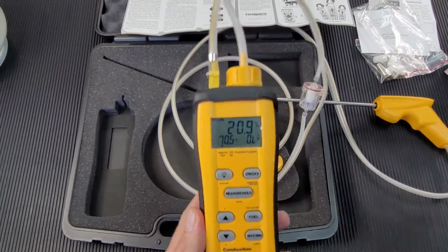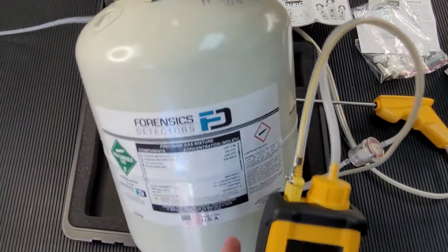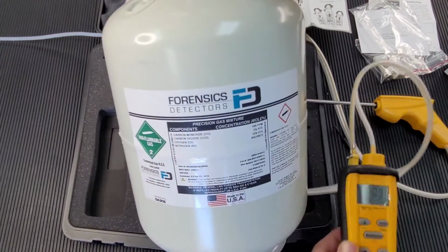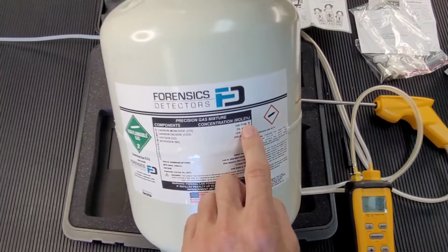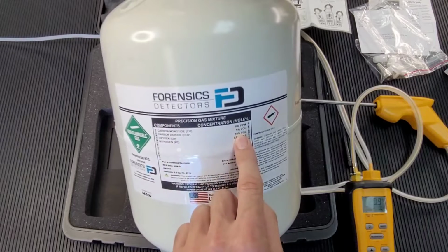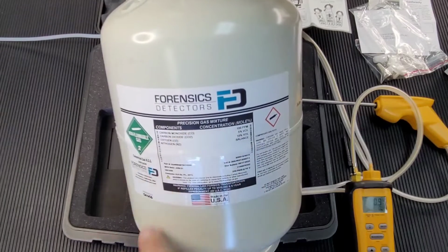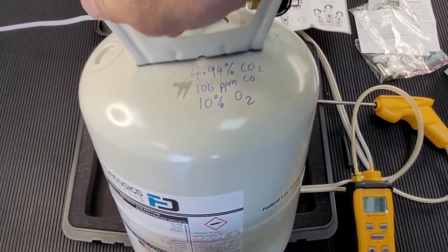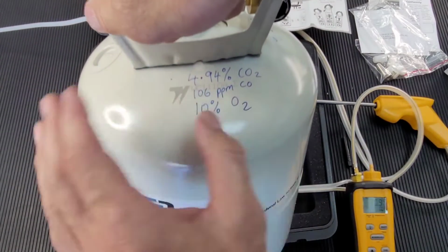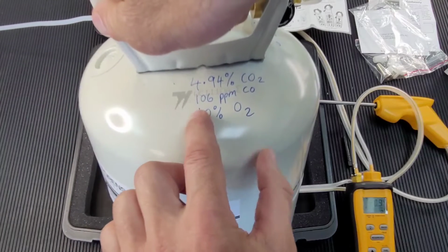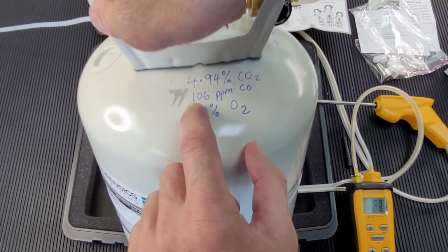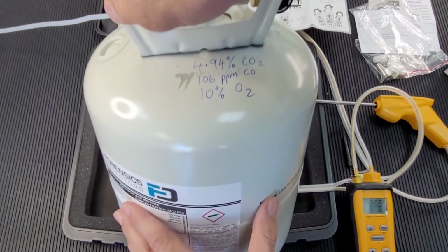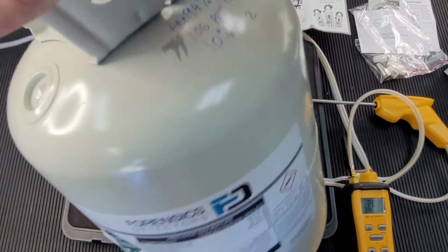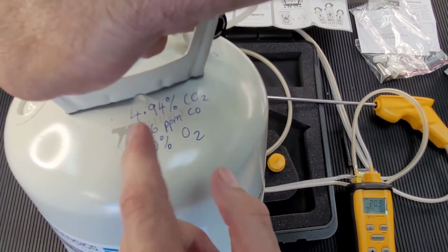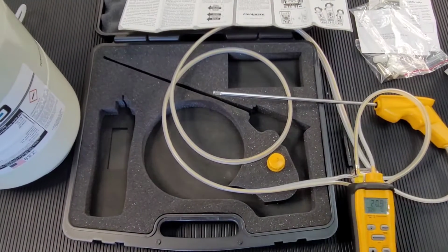Okay, so what we're going to do now is I'm going to rig it up for a test to my calibration gas, which is right over here. It has carbon monoxide 100 ppm, oxygen at 10%, and we have nitrogen and carbon dioxide. Okay, folks, sort of mimicking a situation in a combustion. Although, of course, there should be more of this or more of that. That's fine. Now, the certificate of analysis wasn't 100 ppm, it was 106. Although I ordered at 100, always check your COA with your gas cylinders to make sure you're looking for the exact amount. Okay, folks, so let me pause and come back.